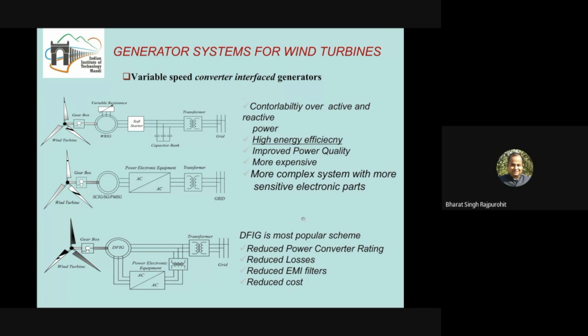Fine. But a few recent studies are also showing, when we are talking about fault ride through capability, it means when the penetration level of wind is very high in a certain country like Germany or Denmark or even in India, and a fault happens, then to bear that fault, remain connected to the grid and once again start giving power to the grid, that capability is higher in a synchronous generator as compared to the DFIG. That capability is giving us a hint that once a very high penetration is there, synchronous generator schemes are better as compared to the DFIG. So now it depends on what the philosophy is. If the philosophy is economics, DFIG is performing better, and if the philosophy is to have better stability, synchronous machines are better.